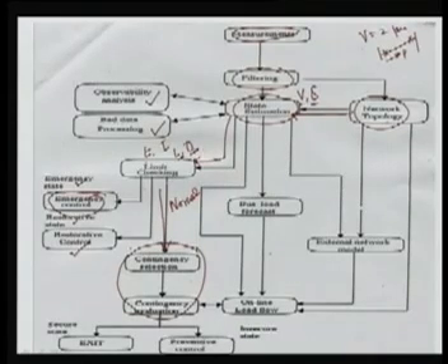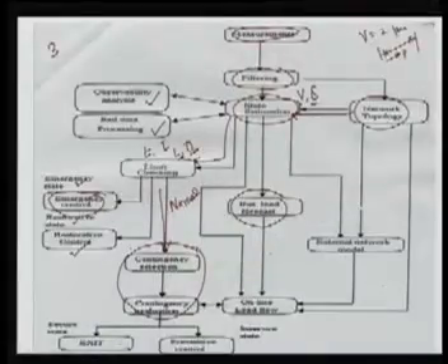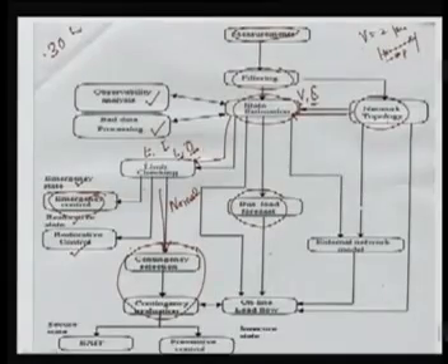Those are, from the state estimation, we get this load forecast. Normally, this whole process, from measurement till all this calculation, is performed in a half an hour interval. So every half an hour we get data from the RTUs, and finally we do all this process, and again after half an hour we get a new set of data. In this half an hour, what happens? Your load keeps on changing, so it will be varying. So we require the load forecast during that period so that we can have exact information about the system state within this half an hour.